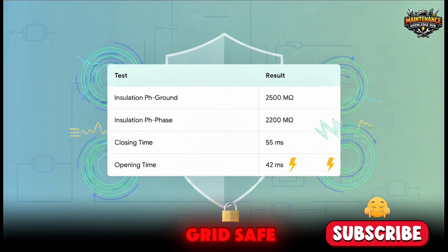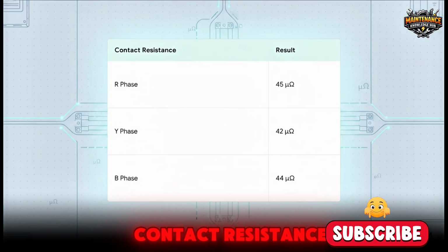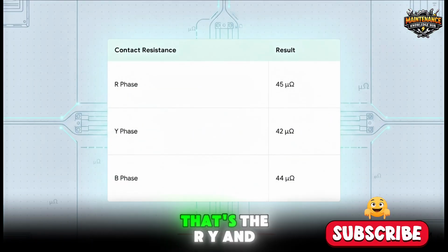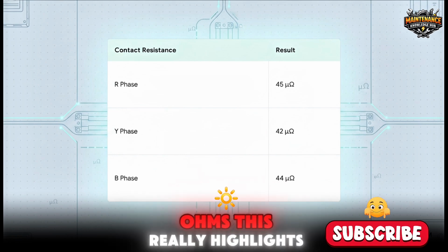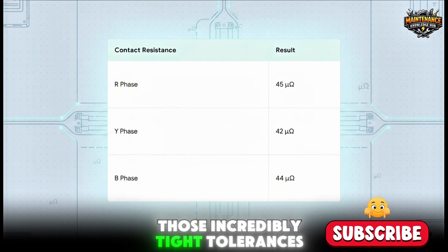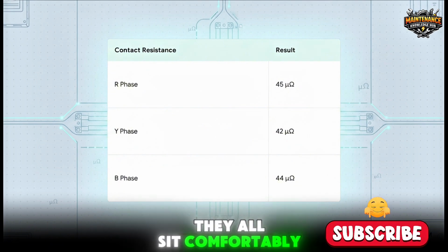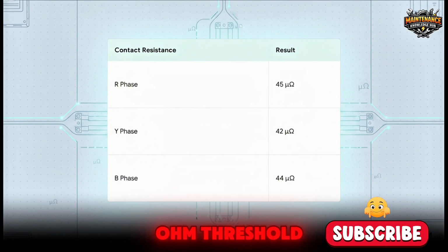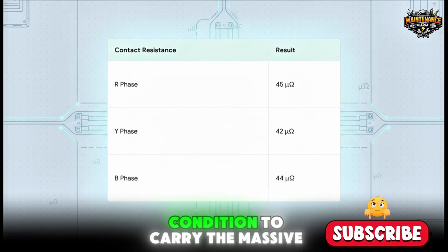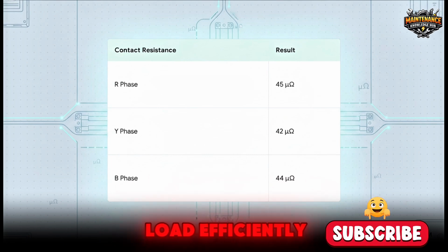And then looking at the contact resistance across all three electrical phases, that's the R, Y, and B phases, the resistance came in at 45, 42, and 44 microohms. This really highlights those incredibly tight tolerances. They all sit comfortably below that 100 microohm threshold we talked about earlier, which basically means the contacts are in superb condition to carry the massive load efficiently.